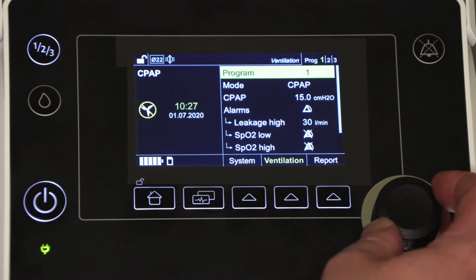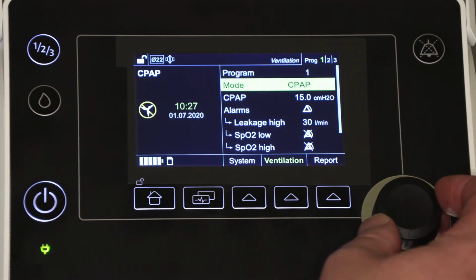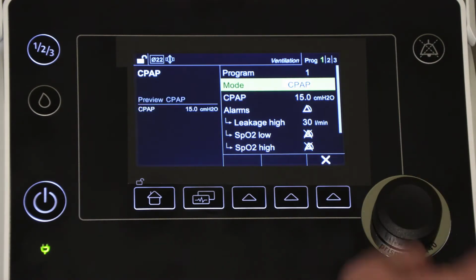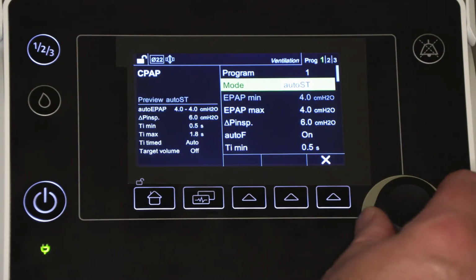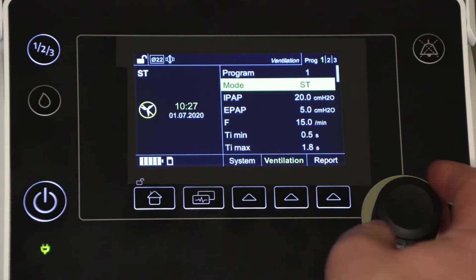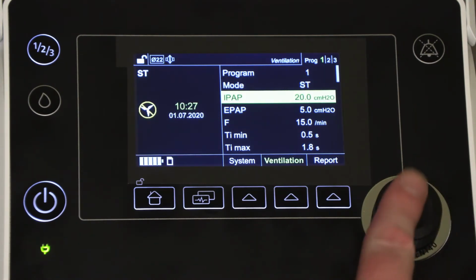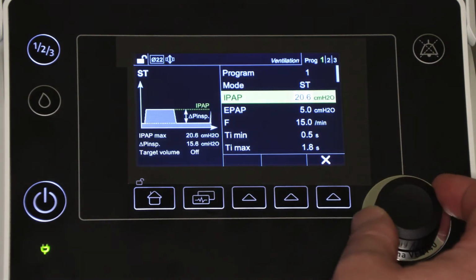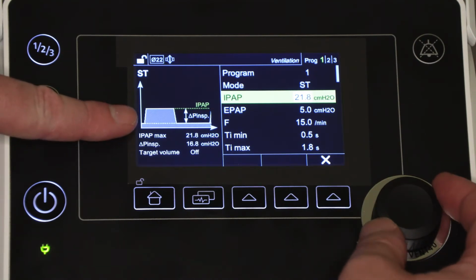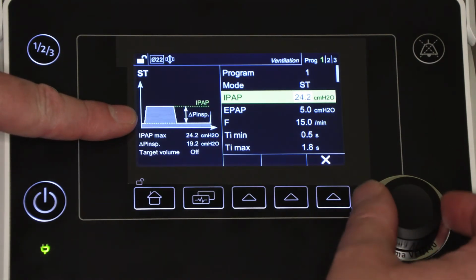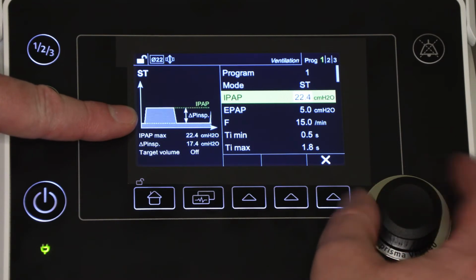Now let's look at ST mode. So enter the ventilation menu again and change the ventilation mode to ST and confirm. Scroll down to select and adjust further settings. Note that as you change a setting, a diagram is displayed on the left side of the screen showing the changes you're making.